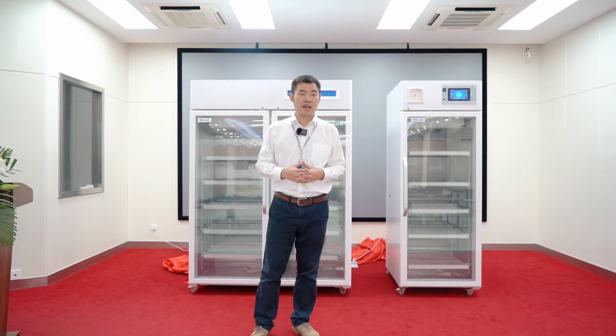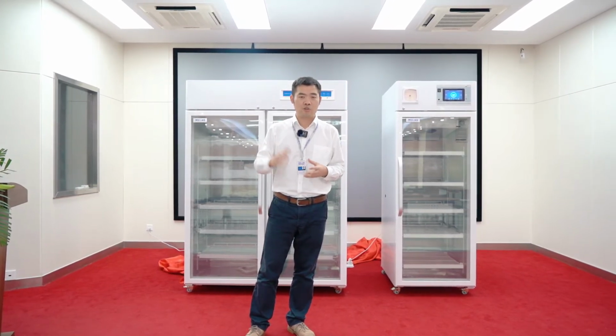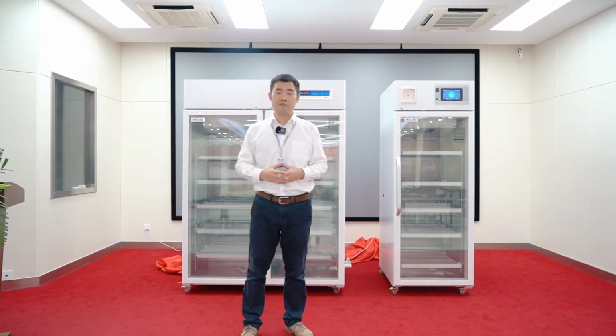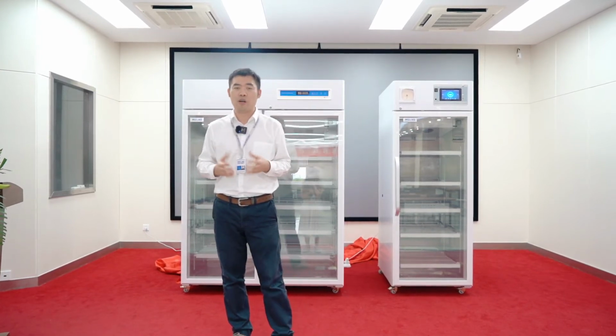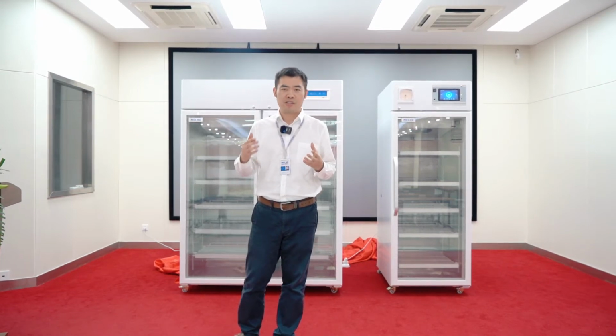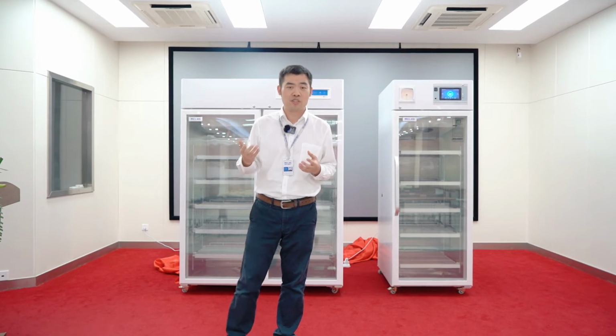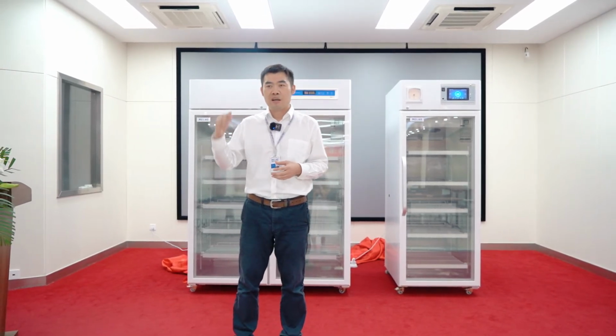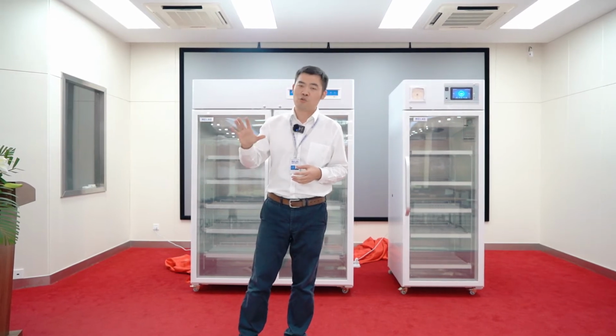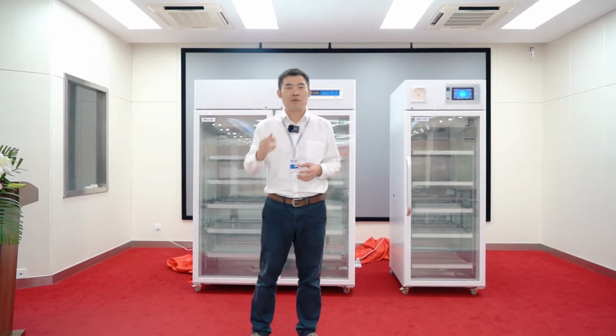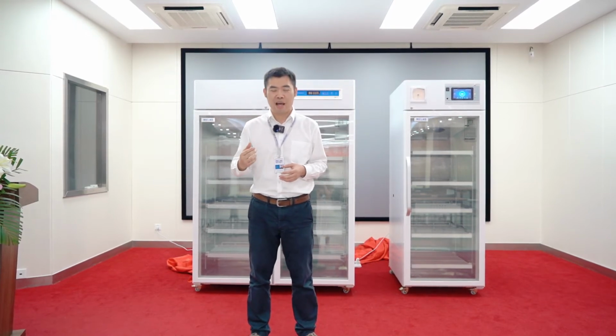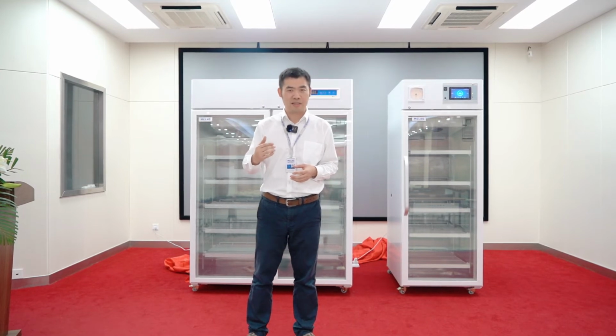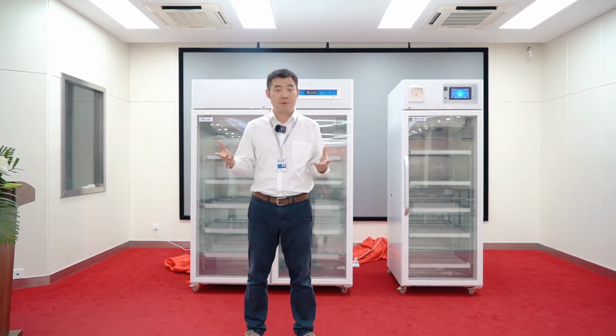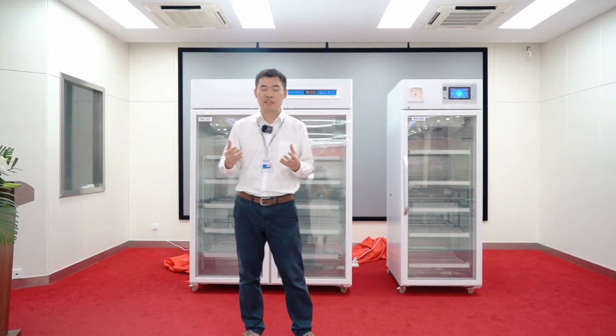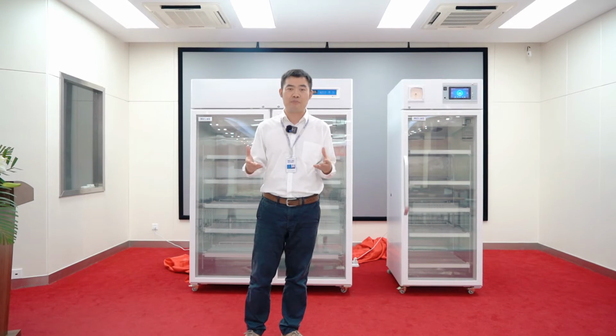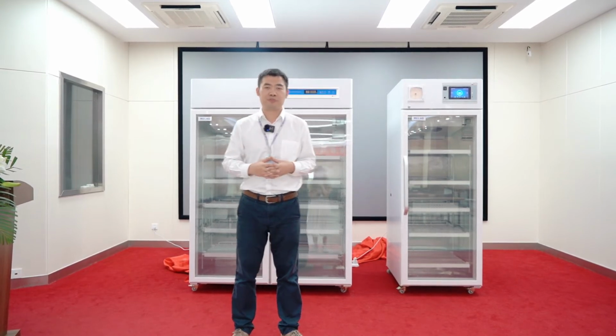Another concept customers really look for is door open recovery. If you look at the lab workflow, they open the cabinet and close the door several times, like 50 to 60 times each day. They really want the compressor to kick in and pull the temperature down quickly back to the set point. Otherwise, the critical samples exposed to the warmer ambient temperature would be damaged.